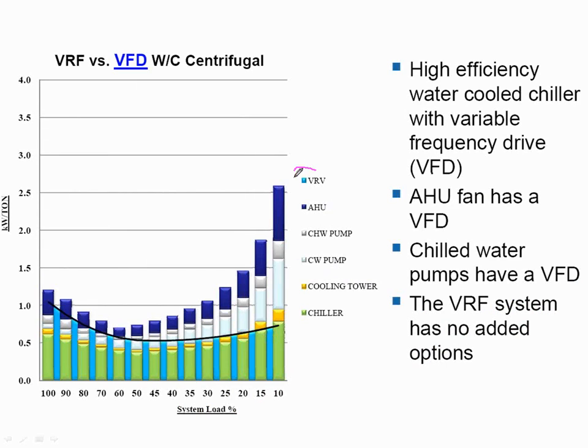So on this chart, in this baby bluish, whatever you want to call that blue color, we have the VRF rating systems in terms of kW per ton at different loading points, right? So at 100% load, 50, 25, 10, etc. That's these blue bars here. So I got this first blue bar right there is my VRF system when he's fully loaded, and his line kind of makes this inverted curve down here. That black line represents all my VRF system ratings at 10 different points.